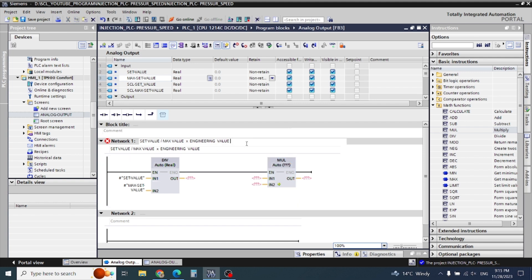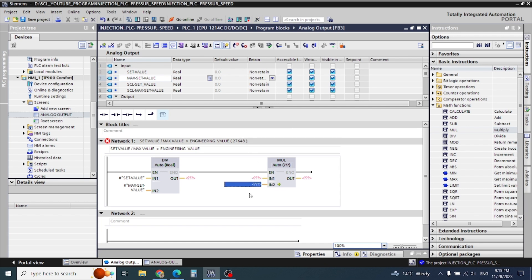The engineering value is how many bits our analog output card has — like 16 bits or 12 bits. In my case I have an S7-1200, so this engineering value is 27648. I will write here 27648.0 because I am using the real value.